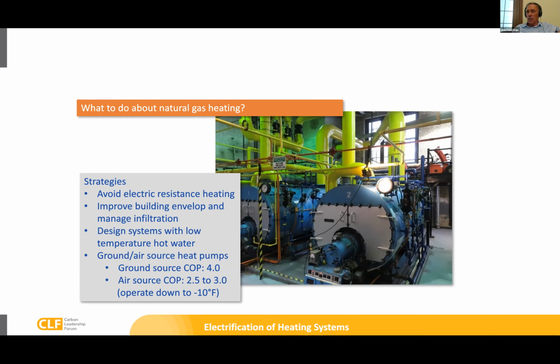The challenge with ground source heat pumps in existing buildings is where do you put the field, and do you have the available land area in an urban environment? Often you don't. But air source heat pumps have come a long way, particularly in the last 5 years. Many of you are familiar with VRF, variable refrigerant flow systems. They're not as efficient as ground source because essentially a heat pump is extracting heat from the outdoors and pumping it up, using a compressor to pump that heat uphill, if you will, and reject it inside. And the steeper that hill, the more energy it requires. So as it gets colder and colder outside, the efficiency and the output of an air source heat pump goes down, whereas with a ground source, the deep ground temperature is pretty much a steady 54.5 degrees, which is primarily why ground source heat pumps are more efficient.